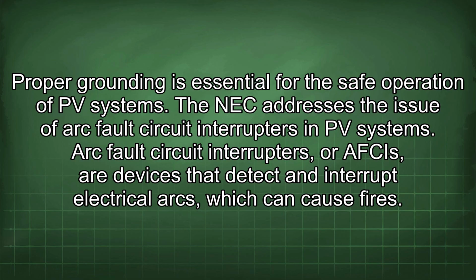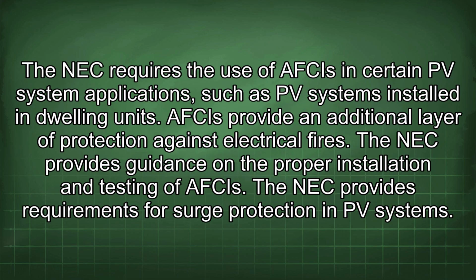The NEC addresses the issue of arc fault circuit interrupters in PV systems. Arc fault circuit interrupters, or AFCIs, are devices that detect and interrupt electrical arcs, which can cause fires. The NEC requires the use of AFCIs in certain PV system applications, such as PV systems installed in dwelling units. AFCIs provide an additional layer of protection against electrical fires. The NEC provides guidance on the proper installation and testing of AFCIs.